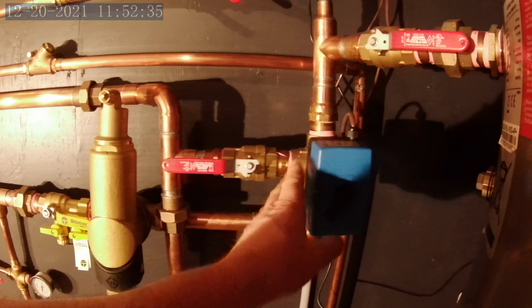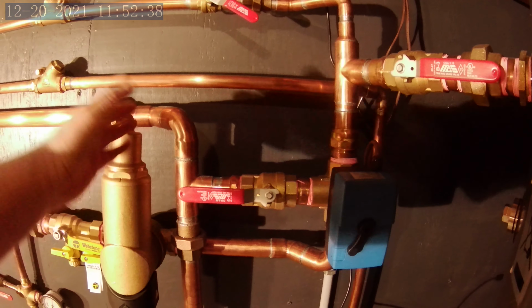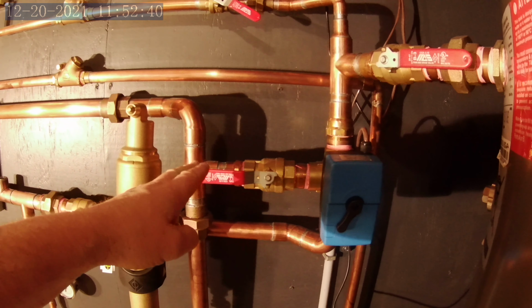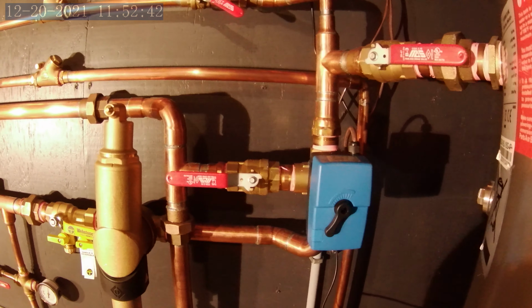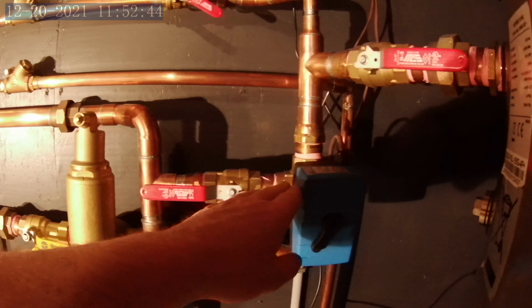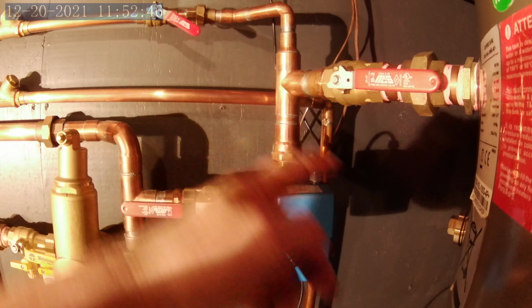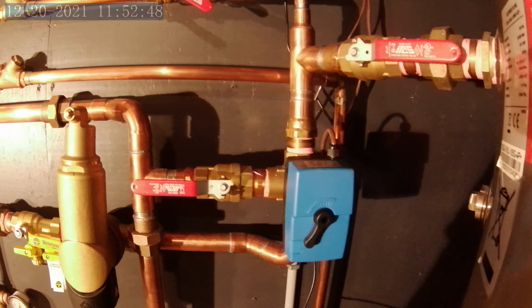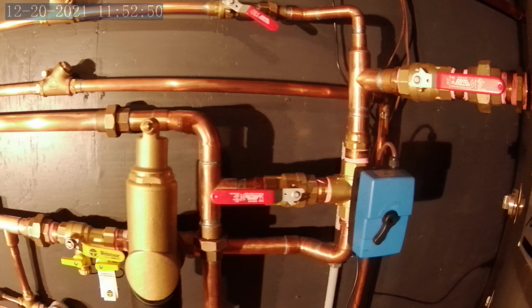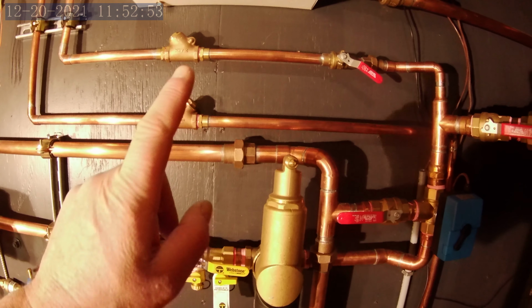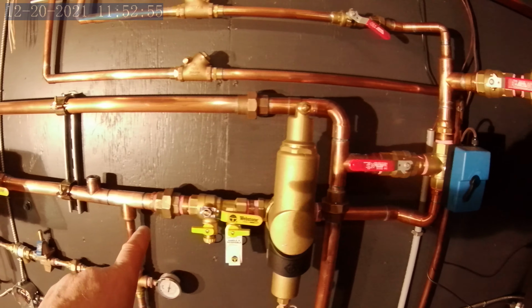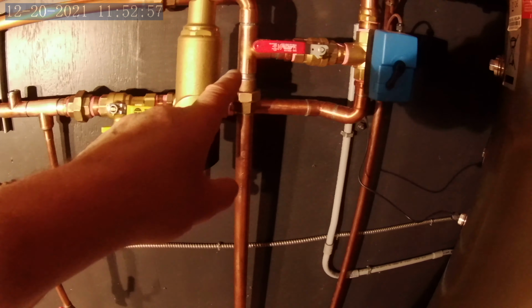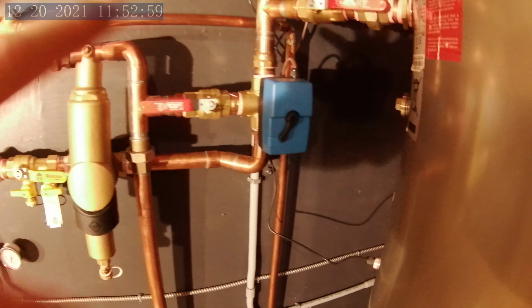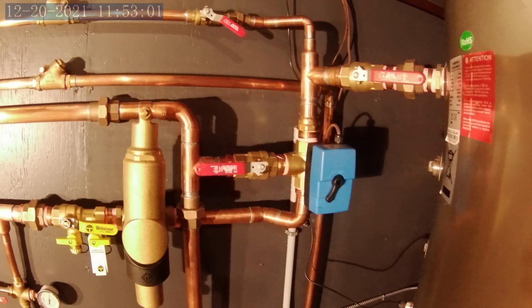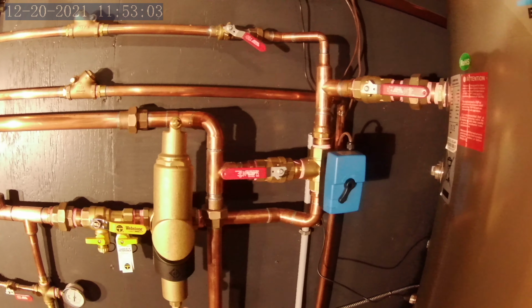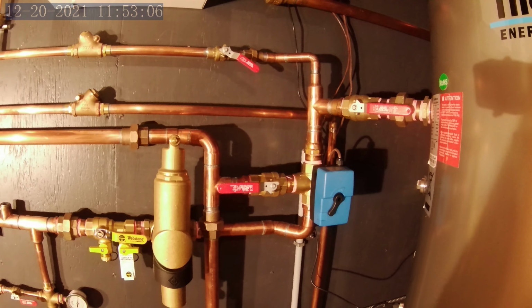The mixing valve takes in a segment of the water returning from the panels, which is obviously quite a bit cooler, to mix in with the boiler, the holding tank water, to mix it down to appropriate temperature. I've got unions on every place that I need it, so that I can take this assembly out and maintain it later on. I won't have to cut and resolder any of the copper.